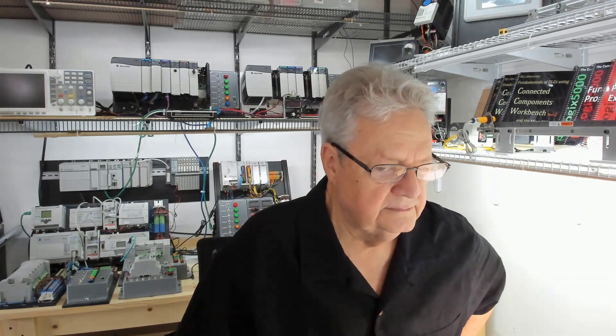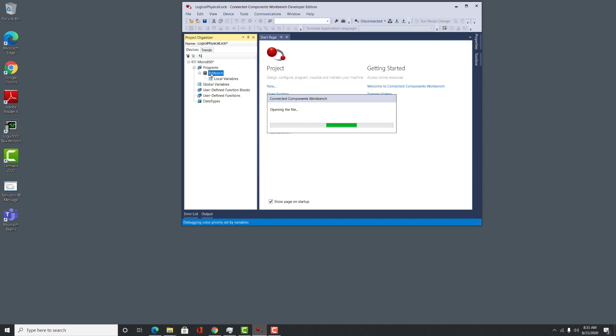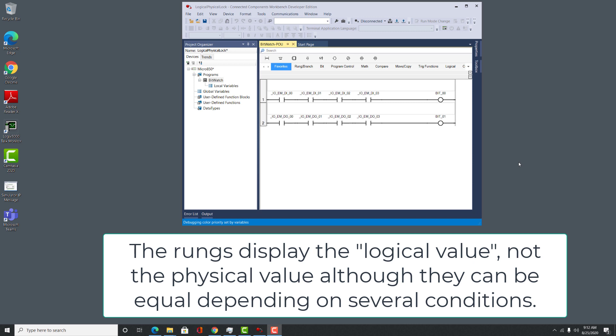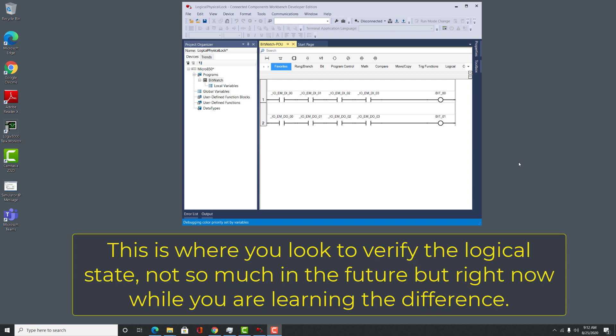Let's go through and demonstrate that. First we create a project and we named our project 'logical physical lock.' In this ladder diagram program file I created some logic — I have a program file with two rungs. They aren't actually logical statements; they are for display purposes only. I want to be able to see the state of these eight bits in memory: four inputs and four outputs. The energized output or direct coils at the end of each rung are just placeholders. The rung has to have an output-type instruction, so I just throw in a direct coil and put a junk bit on it — bit 0, bit 1. What we're wanting to see is the state of digital input 0 through 3 and digital output 0 through 3 as we play with the graphical user interface.